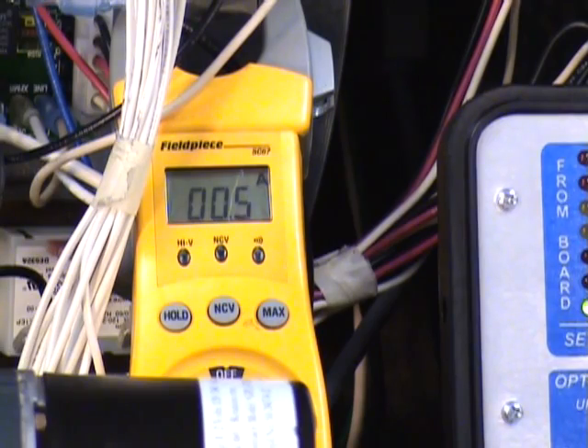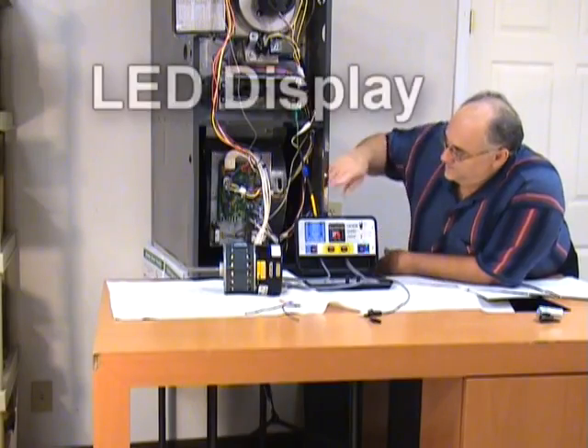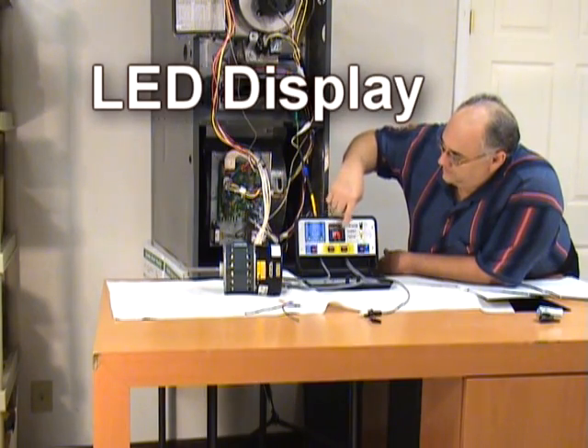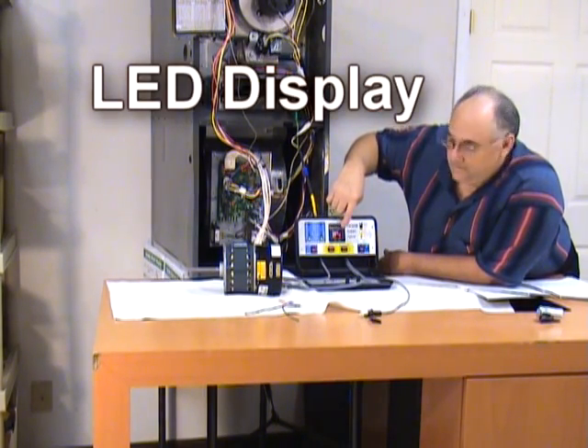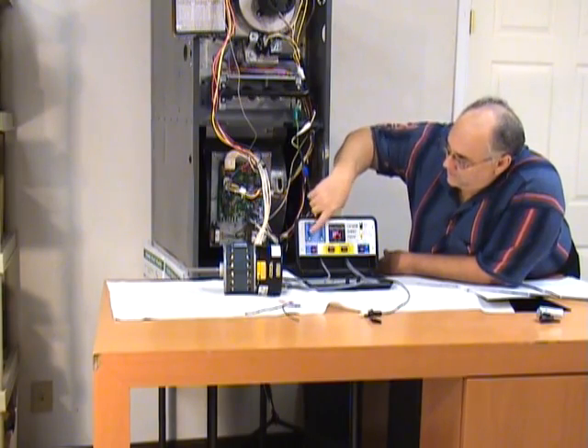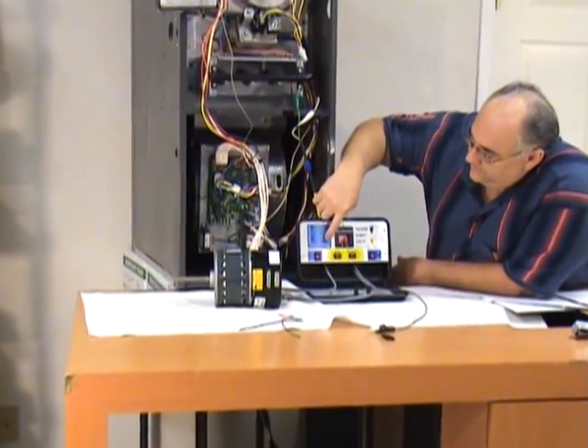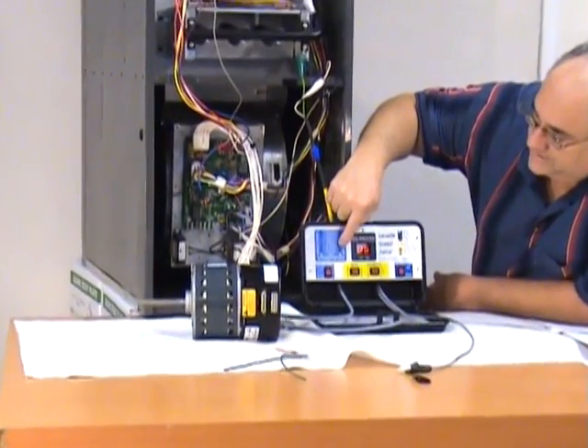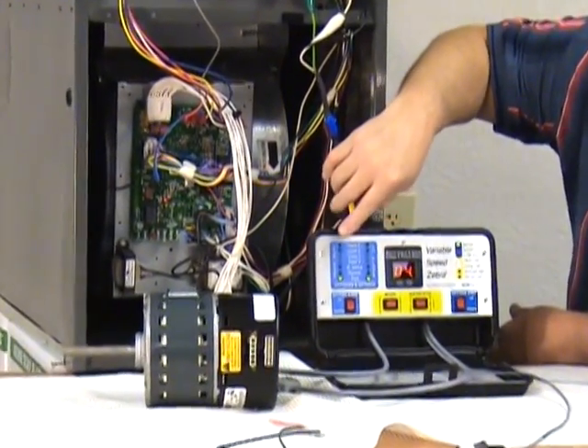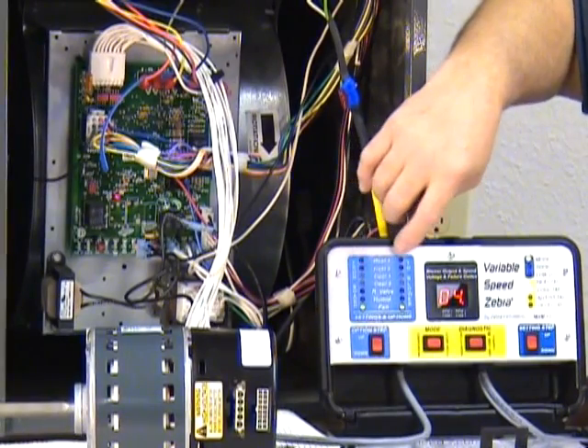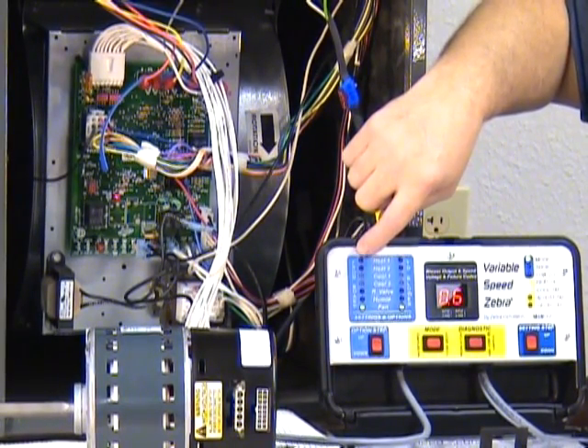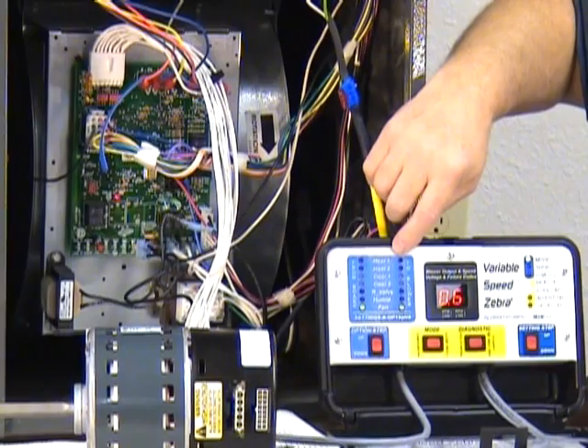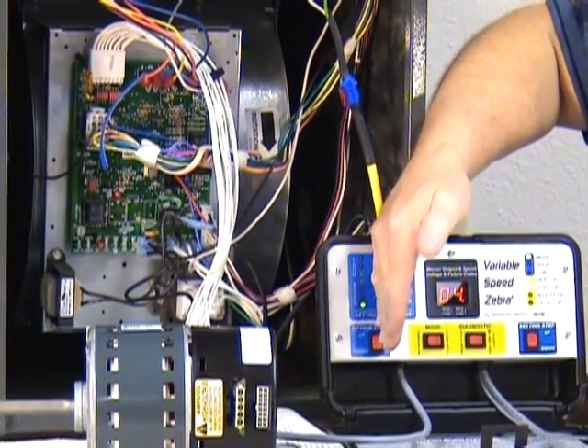Remember that as you're designing duct systems. Make these things as restriction free as possible if you want to keep your customer's total SEER in a high range. So besides our CFM and RPM display, which we're seeing on the variable speed Zebra, you see there's two sets of green lights on here. We chose green for the fan since it's a common color to represent it. There are two sections: one is labeled from the board and the other is to the blower. With the variable speed Zebra, you monitor both sides.